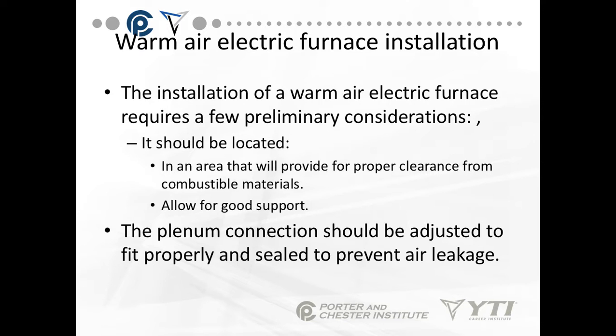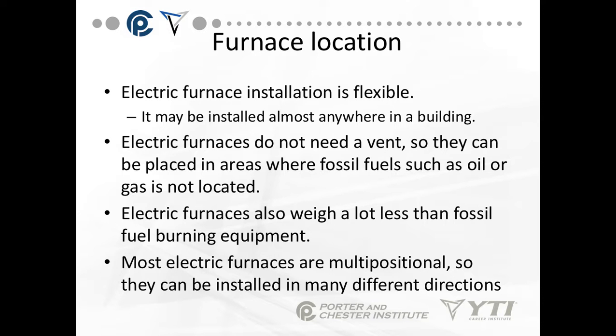The installation of a warm air electric furnace requires a few preliminary considerations. First, it should be located in an area that will provide for proper clearance from combustible materials and has good support. The plenum connection, that's the ductwork connection, should be adjusted to fit properly and sealed to prevent air leaks. Electric furnace installation is flexible. It can almost be installed anywhere within a building.